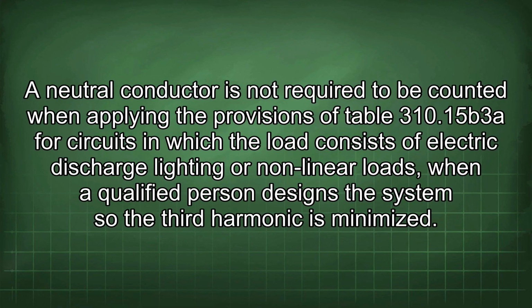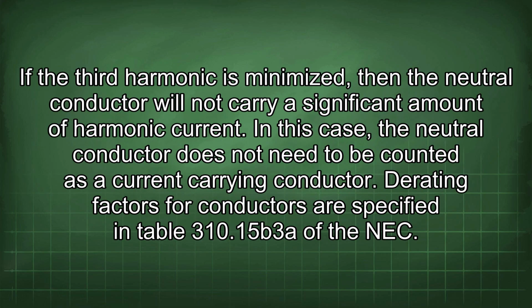A neutral conductor is not required to be counted when applying the provisions of Table 310.15(b)(3)(a) for circuits in which the load consists of electric discharge lighting or nonlinear loads when a qualified person designs the system so the 3rd harmonic is minimized. If the 3rd harmonic is minimized, then the neutral conductor will not carry a significant amount of harmonic current. In this case, the neutral conductor does not need to be counted as a current-carrying conductor.